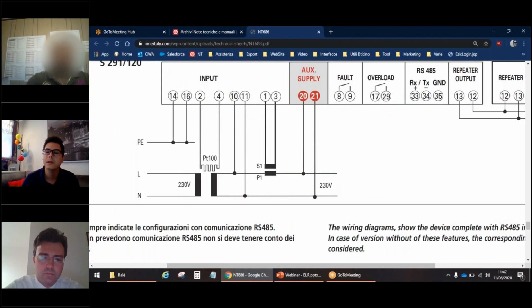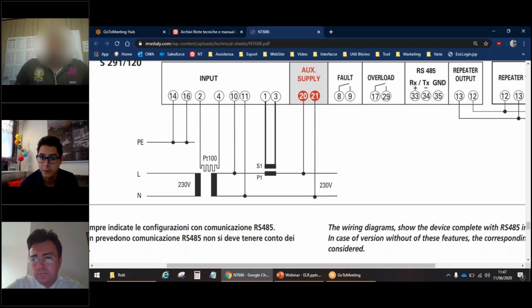As you can see on the wiring diagram, you only have to connect this instrument from the PE to the line, and you are also able to connect a PT100. It's a sensor, a temperature probe, that can avoid overheating of the transformer. You can also connect a current transformer that can keep under control the current value that flows from the isolation transformer. That's all for the current transformer.